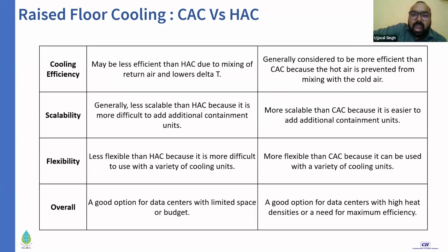They are also considered more efficient in nature, because since you have abundant cold air inside, you don't need to very strictly maintain the supply air temperature. A minor fluctuation can be easily handled by the server because the air abundance is more. The short cycling and other problems you feel in cold air containment are less frequently observed in hot air containment.